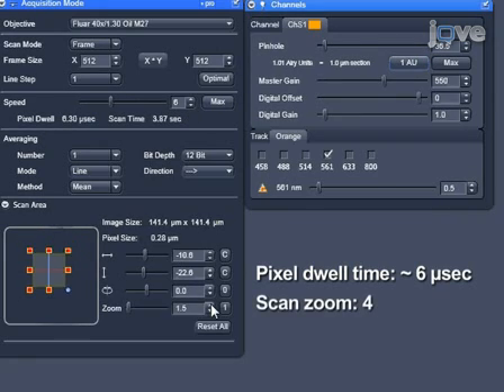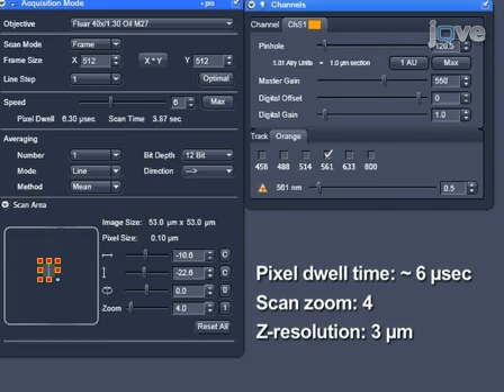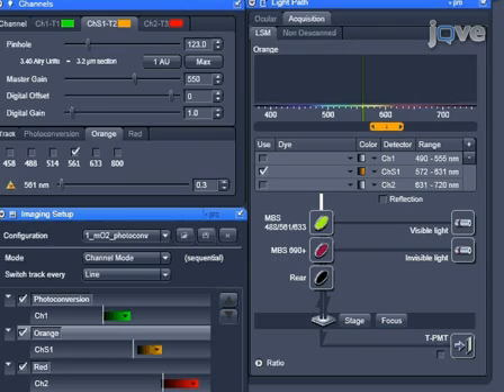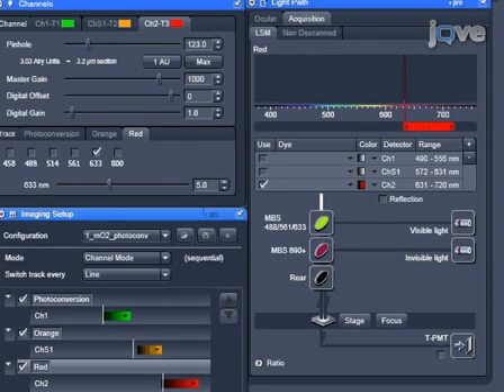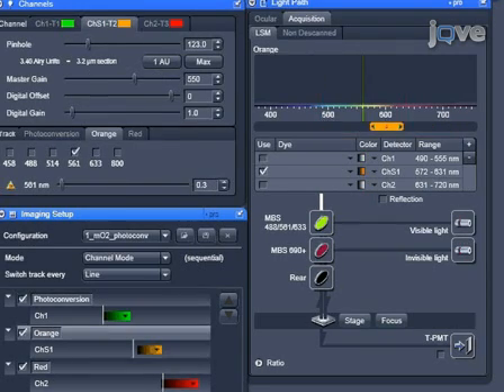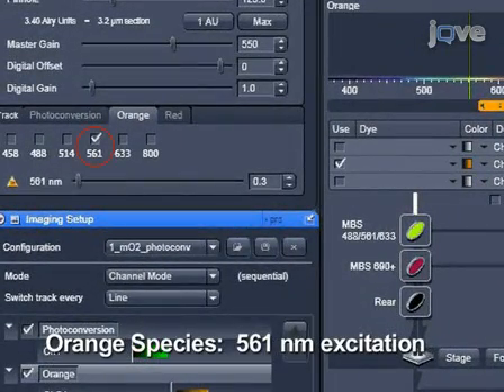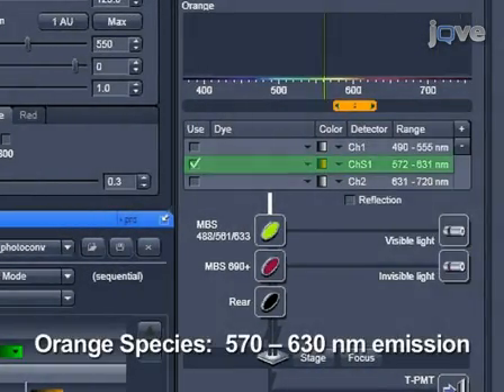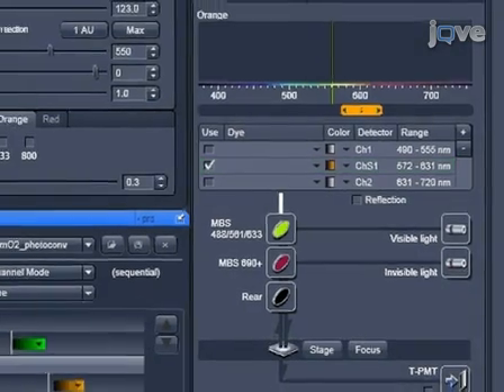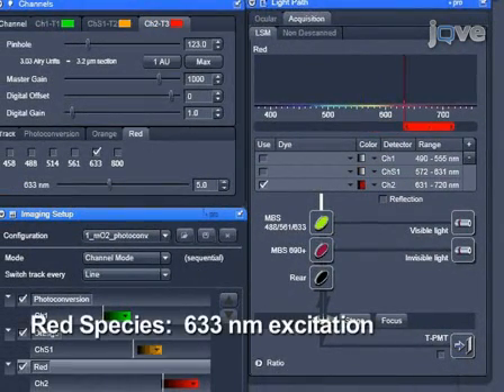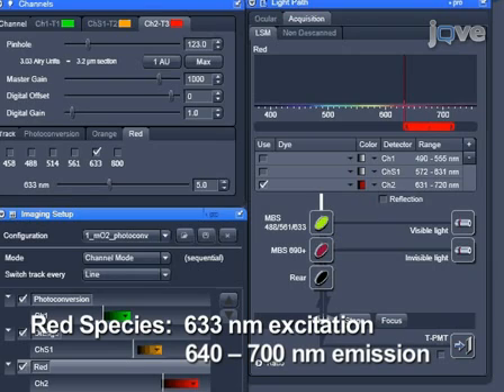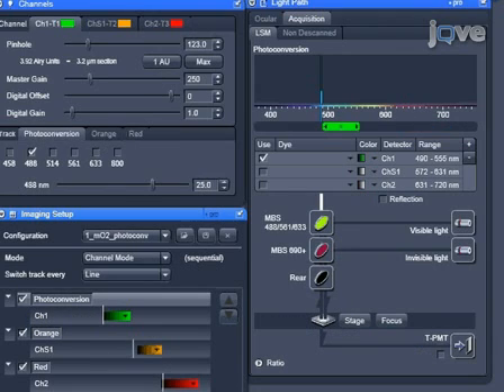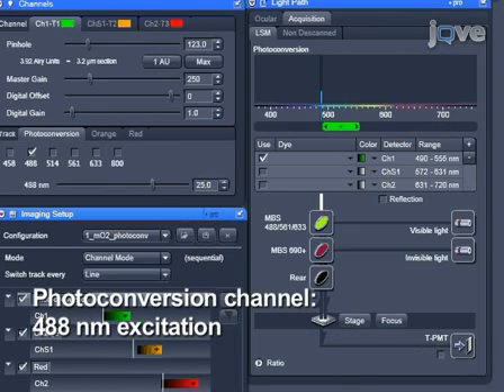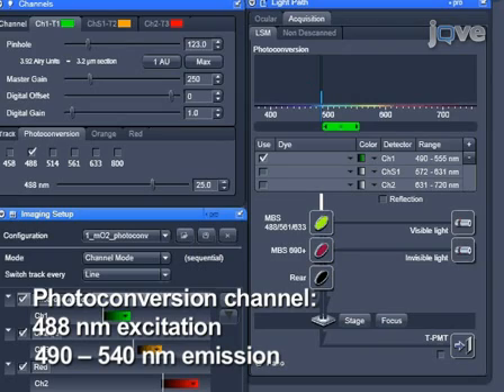Set the scan zoom to 4 and increase the pinhole size to match a Z resolution of 3 microns. Configure 2 detection channels for the initial and photoconverted fluorescence, as well as a photoconversion channel. Observe the orange species using 561 nanometer excitation light and collect the fluorescence between 570 and 630 nanometers. Detect the photoconverted red species using 633 nanometer excitation light and collect the fluorescence between 640 and 700 nanometers. For the photoconversion channel, select the 488 nanometer laser line and collect the fluorescence between 490 and 540 nanometers.